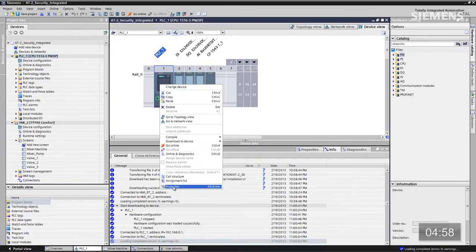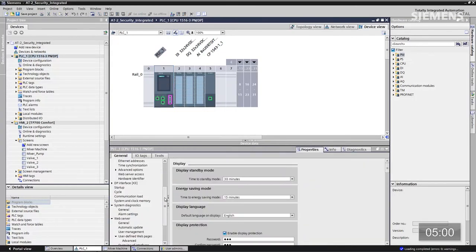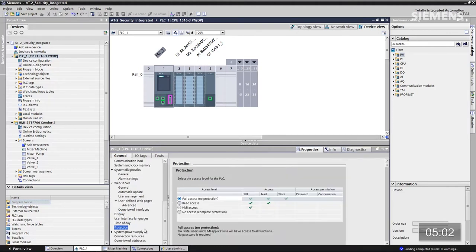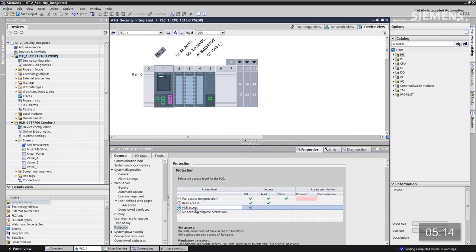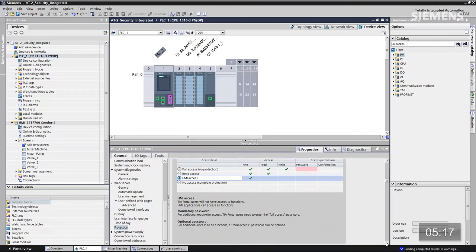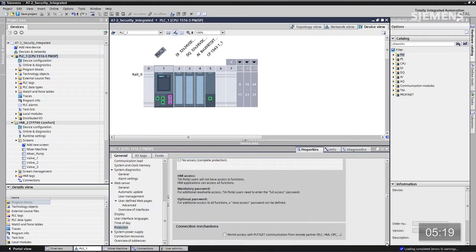Et qu'en est-il du contrôleur et de son programme ? Je sélectionne la CPU principale, je vais dans les propriétés et tout en bas je clique sur Protection. On y trouve les trois niveaux d'accès habituels : accès complet, accès en lecture, et accès IHM. Un nouveau niveau est aujourd'hui disponible, à savoir « pas d'accès » au niveau 4. Je vais cliquer sur l'accès au pupitre opérateur et descendre jusqu'au mécanisme de connexion. On voit que les communications Get and Put, depuis un serveur OPC ou un système SCADA, ou de contrôleur à contrôleur, sont toujours activées si j'ai accès au pupitre opérateur.